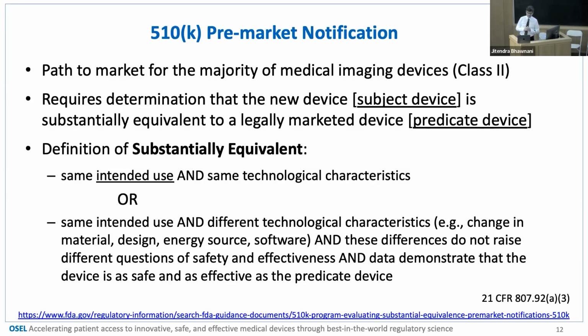So starting with the most common process, this is the 510(k) pre-market notification. That's for class 2 devices, which is the vast majority in our field. The way it works, in plain language, is you need to show that your device is equivalent to a previous one that is already cleared. We call the new one the subject device, and the old one is the predicate device. And whoever is sending the submission is called the sponsor or the manufacturer.